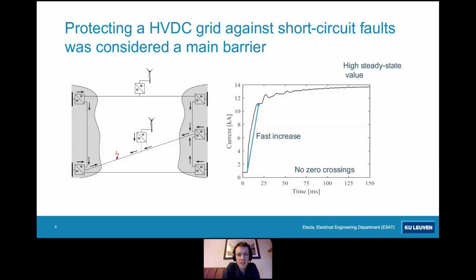Now, to go to an HVDC grid, there were some main barriers. One of these barriers was the protection of this HVDC grid against short circuit faults. If a fault occurs in an HVDC grid, we see that the fault current shows a very fast increase. In the picture that we see here, we have an increase of 10 kiloamps in about 10 milliseconds, and the fault current goes to a high steady state value. In the meantime, we don't have any zero crossings, so we cannot use traditional AC breakers to interrupt this fault current. By contrast, the power electronics in the converters cannot withstand high overcurrents for a long time. So that means that we have to interrupt the fault current within the first few milliseconds.